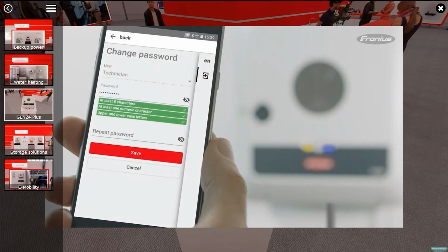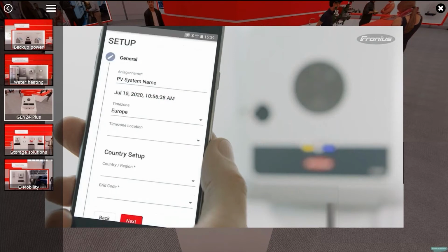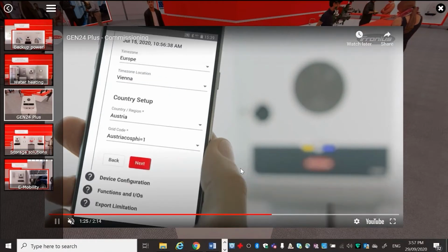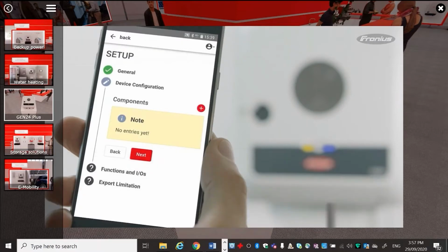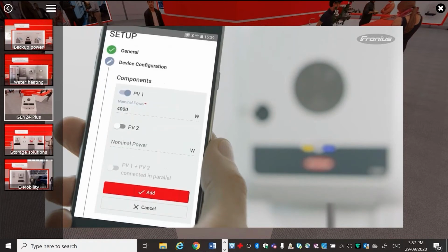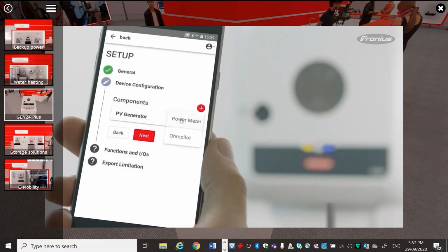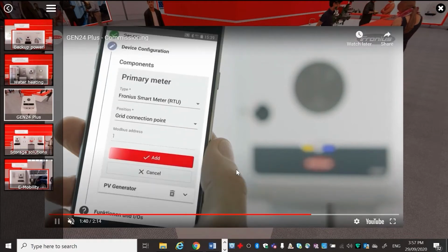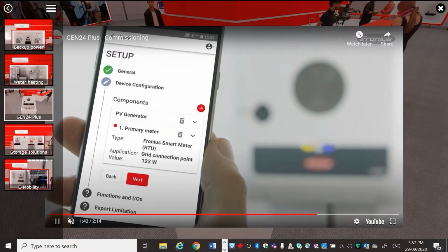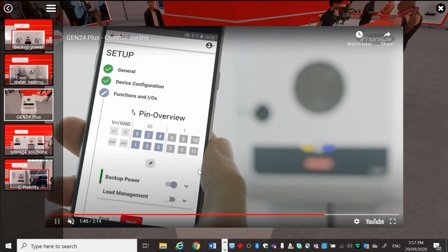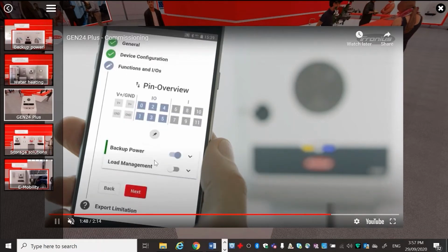Now the next part is to set the settings on the inverter. You will need some technical settings set up, entering all the general information like the PV generator on the system, and also entering all the components. So if you have a smart meter installed, for example, just add every other component. You can also set up the backup solution, or export limitation, on this product page.